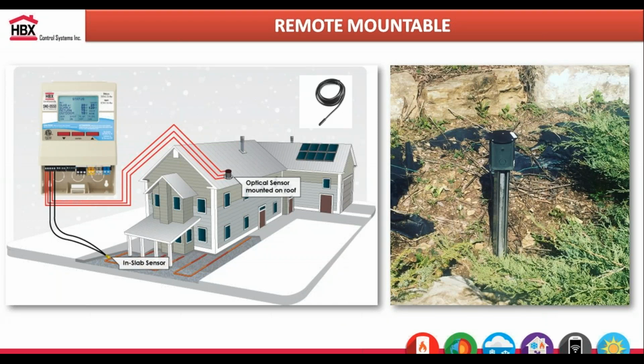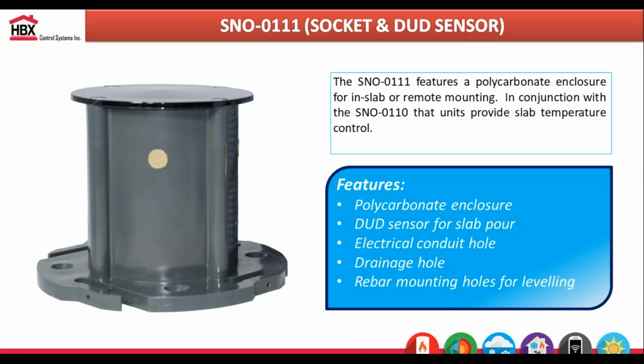It doesn't necessarily have to be in the slab. There are a lot of different reasons why you wouldn't want to have a slab. Maybe the slope is really steep, or maybe you want to use pavers and it's not an option to put the sensor into those pavers. So you can mount this on a roof or in a flower bed. A lot of people will just mount it on the fence, and then with the rubber coated 10K sensor, which comes with the optical sensor, you would just need to put that into the slab to feed back the temperature of how hot and how cold that slab is to the controller. So you have the capability of putting it in the slab and outside with that remote sensor.